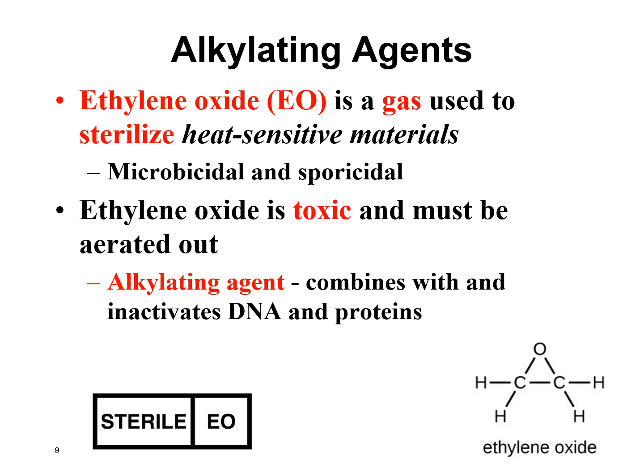It has to be aired out really well before you would open up the ethylene oxide sterilizer. So it does take a couple hours to run a cycle and make sure the gas is all removed before you open the chamber. And if you do breathe in the gas, it's very irritating. It can make you throw up, and it can also cause cancer. So it's not a very good one to be around.